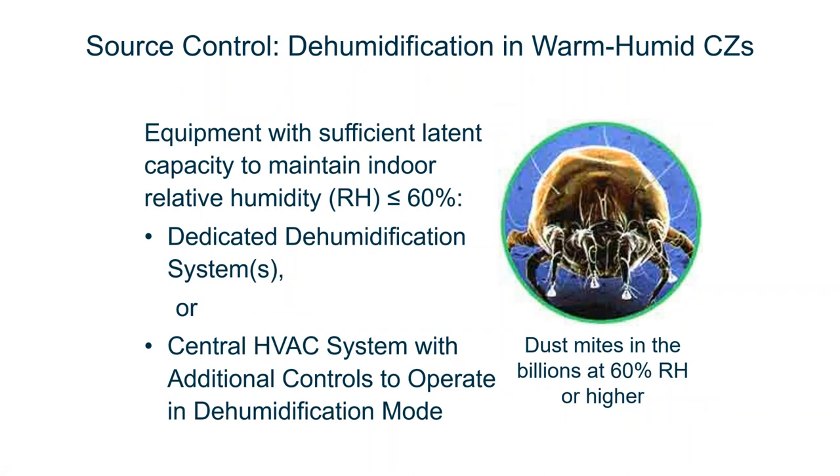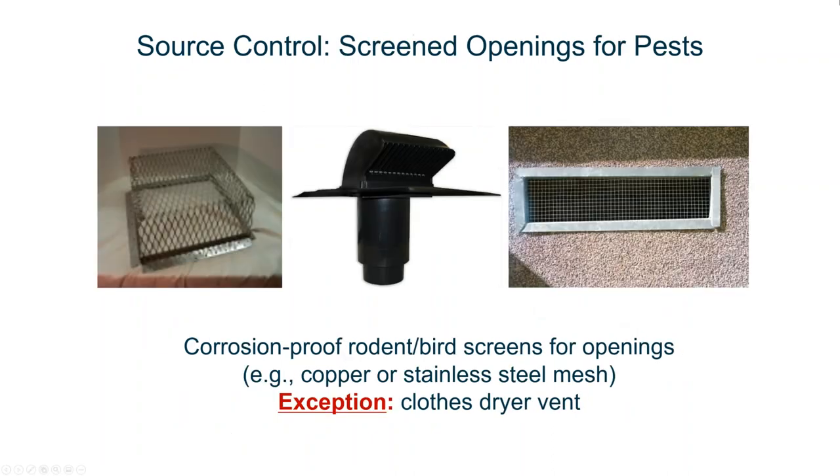You also want to reduce biological contaminants by keeping dust mites out, and you can do that by keeping relative humidity at 60 percent or below. The dehumidification strategies are not only important for moisture control and comfort, they're important to keep dust mites from growing to the billions in our homes, in our sheets, in our carpets, everywhere throughout our home. You also want to keep pests and biological contaminants from entering spaces. Using screen vents is an easy, low-cost measure. The only place you don't do this is your dryer vents, because that will collect lint and block the function of the vent.